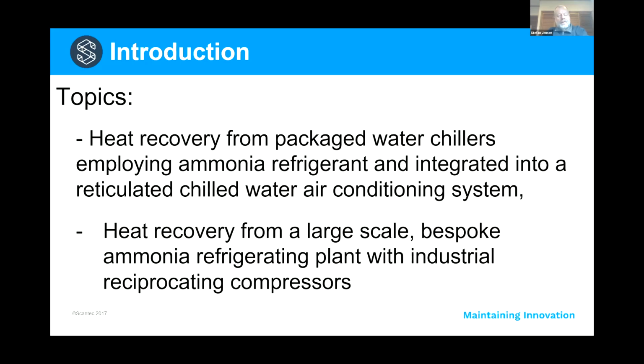And the other one is a very large plant. It's a 500,000 cubic metre cold store where we've fitted a desuperheater to the discharge pipe, the common discharge pipe, out of the ammonia compressors to recover some high-grade heat there that's used for a number of purposes in the plant.